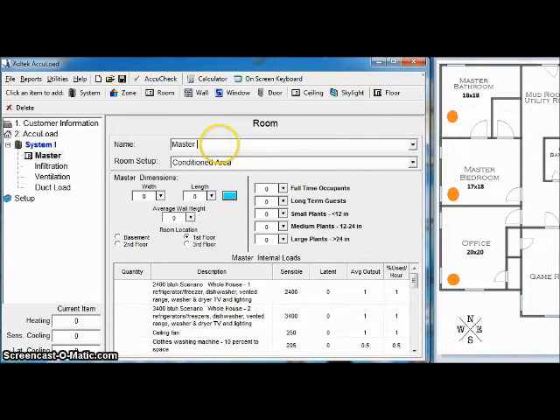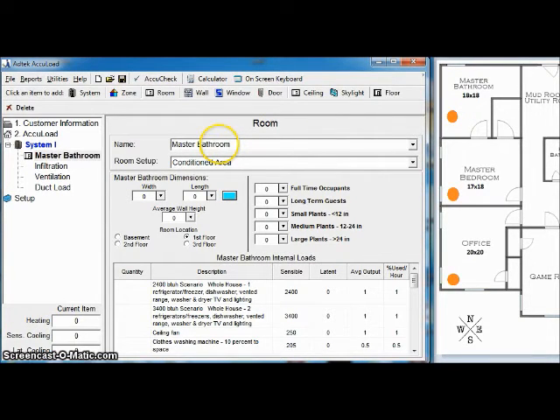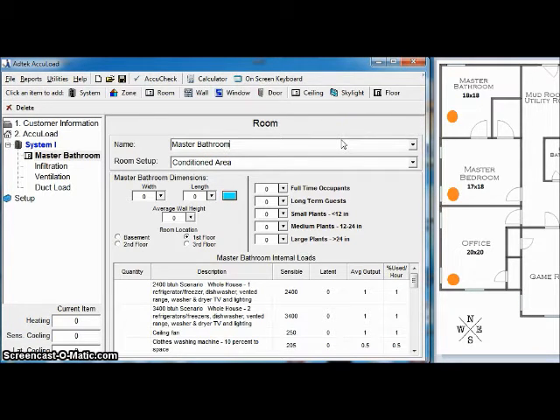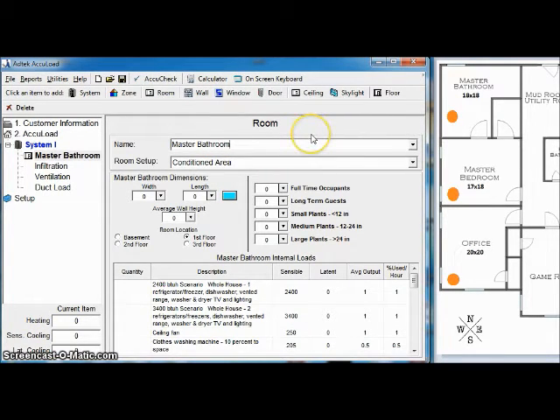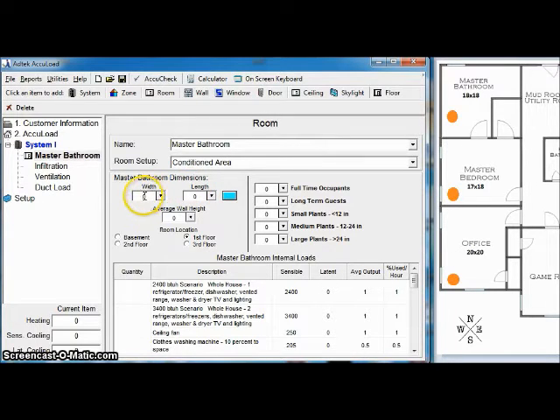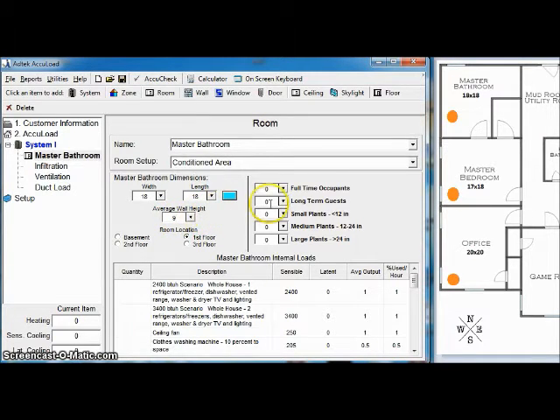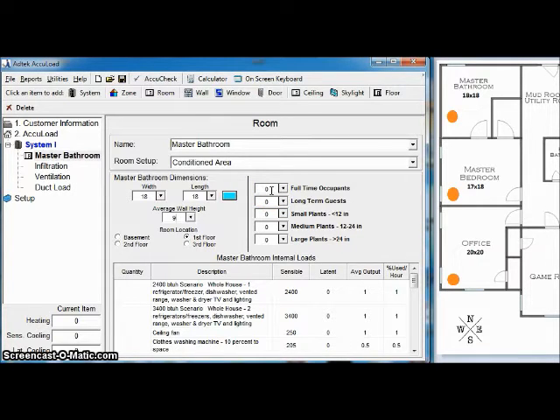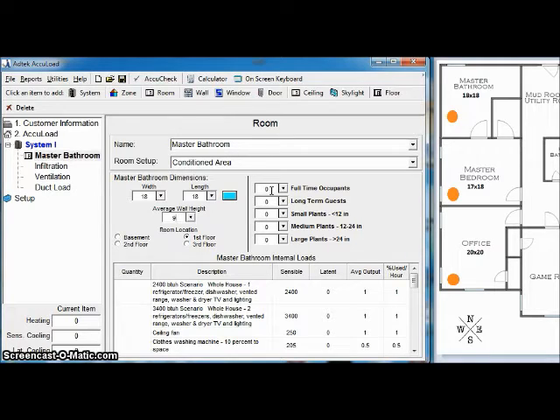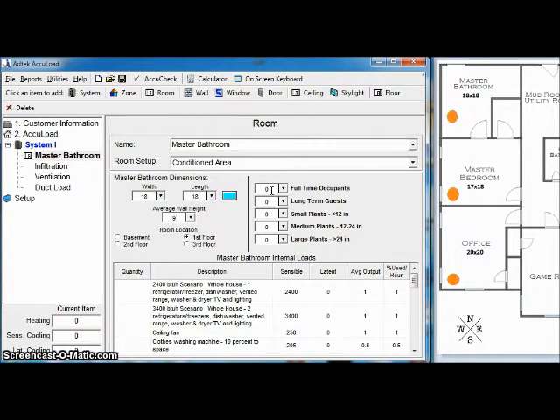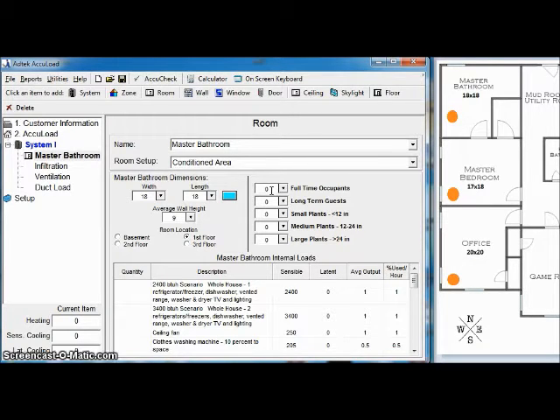So I'm going to type in master bathroom. And as you can see on my little drawing that I have pulled up next to the program, it is not included with the program. Our master bathroom is 18 by 18. Our wall height is 9 feet tall. Obviously, we're not going to put any occupants in the bathroom. Manual J, if you're doing a room by room, Manual J suggests you put the occupants where you think they'll be at 6 PM. Some people will throw them in the living room. Some people will put one person in each bedroom. It's just a matter of your preference.